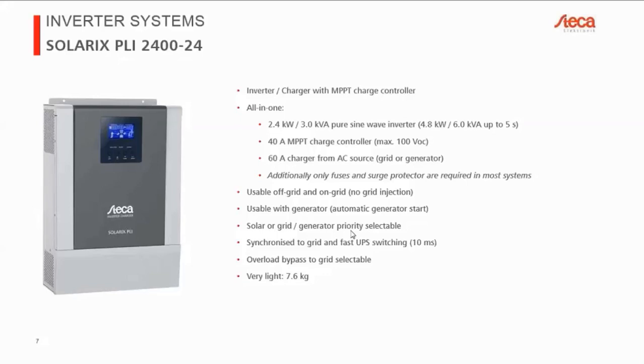Then there's an overload bypass function as well. So if, for example, you're using more than 2.4 kilowatt, then the inverter can automatically switch over to the AC source, for example, the grid, so that you can even take up to 5 kilowatts or 6 or 7 even from the grid. And as soon as it's finished, of course, there's a certain timeout, so you don't switch back and forth too often. As soon as it's finished, it then switches back to off-grid mode if that's your priority. And finally, it's very light at 7.6 kilograms.